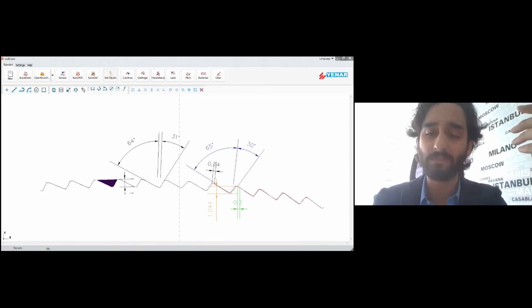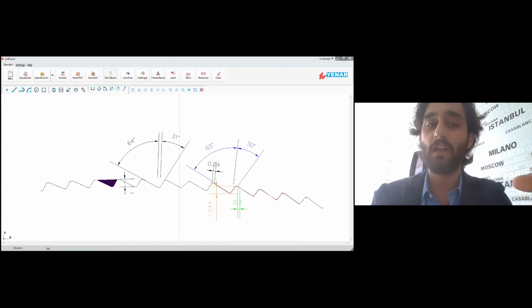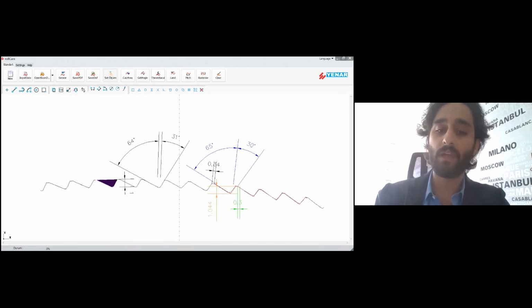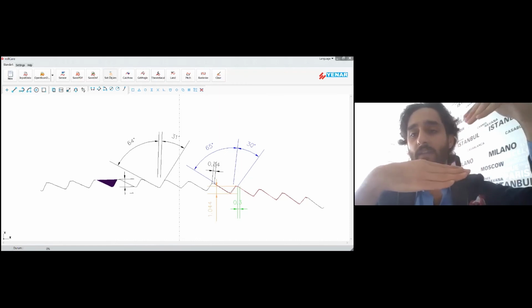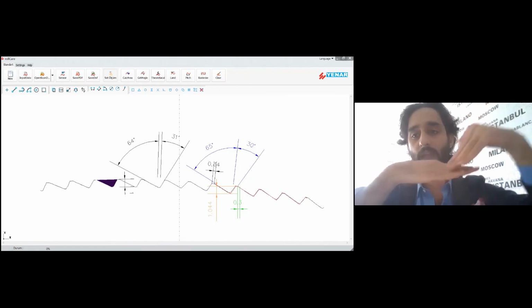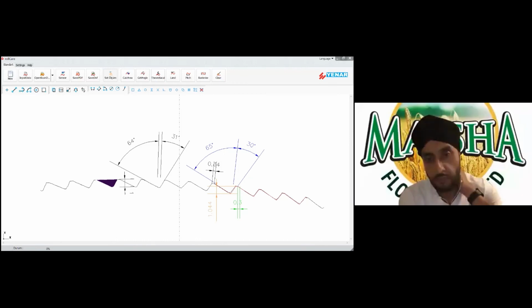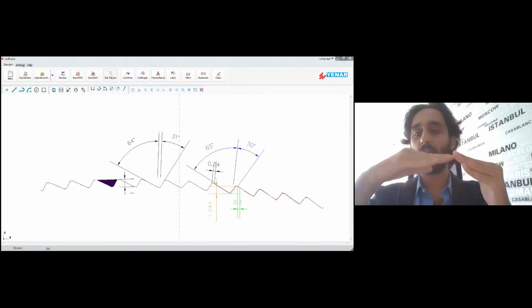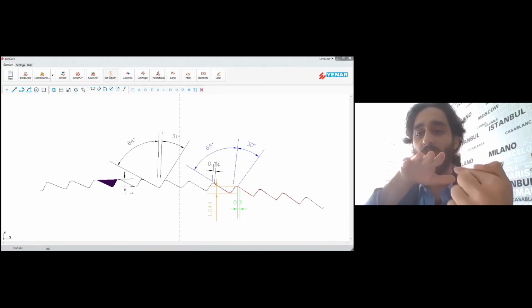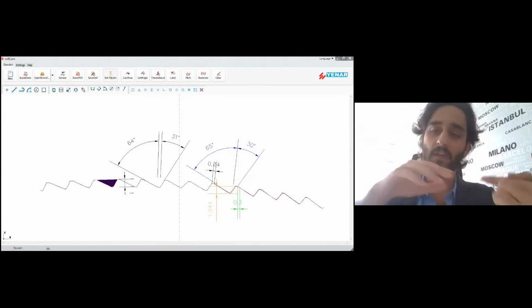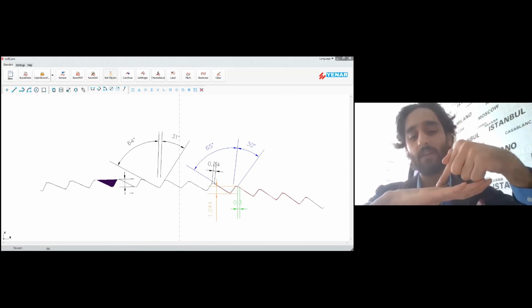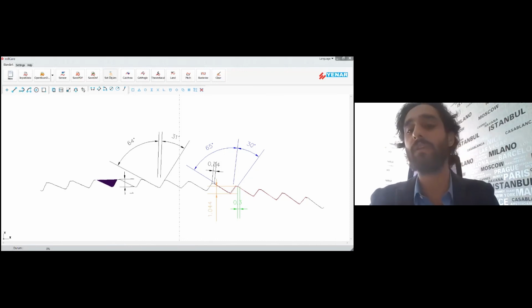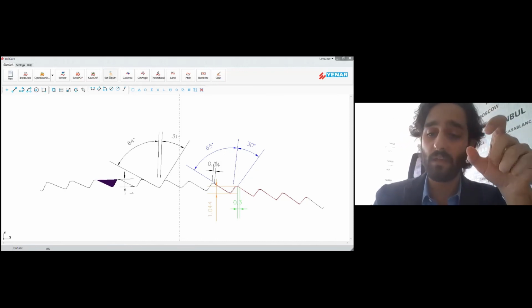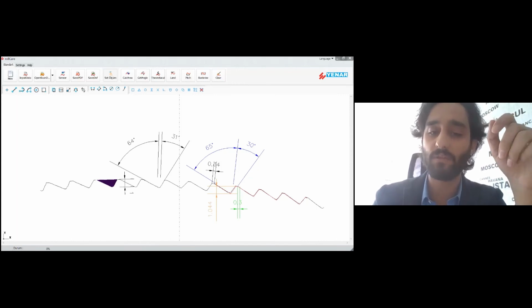But this device works by taking a photo of the roll surface, and as far as the optic device is not placed in the face of the roll, the measurement uncertainty will be high. For example, this is the roll surface, and you are taking a picture at an angle. You have to take the photo from straight on to see exactly what the length of the flutes is, because taking it at an angle creates a parallax. So the length value won't be parallel, and this gives you a false measurement.